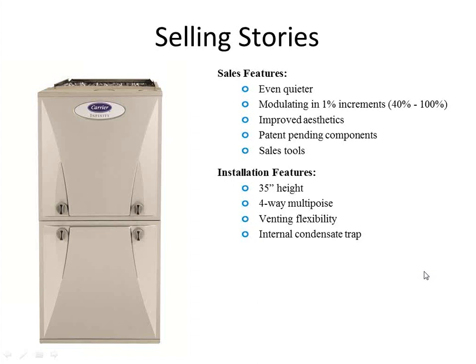The height is pretty short. These are 35 inches. For you guys that have used Carrier and Bryant furnaces prior to 2012, you probably know they're like 40 inches tall. So these guys are about 5 inches shorter than any Carrier or Bryant that you might be replacing at someone's house. So that does give you some more room to install widgets and accessories like humidifiers, RGF light bulbs, and that kind of stuff that needs to be on the discharge of the evaporator coil, or even higher, taller evaporator coils. As you know, some of these ones have gotten pretty ridiculously tall, so the shorter height furnace gives you that flexibility.